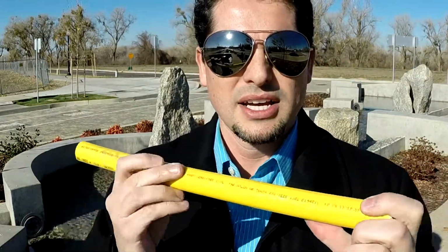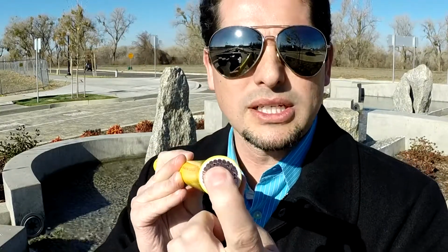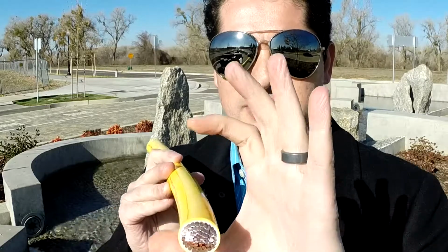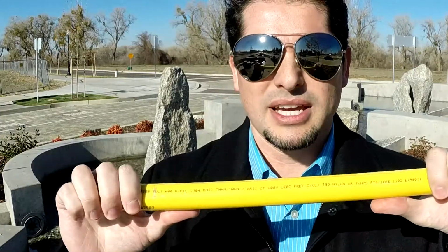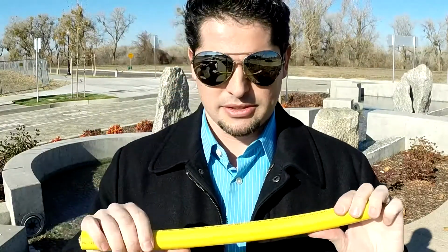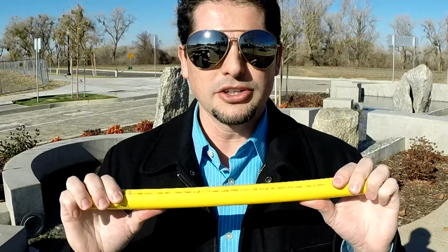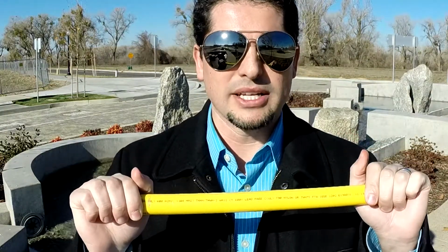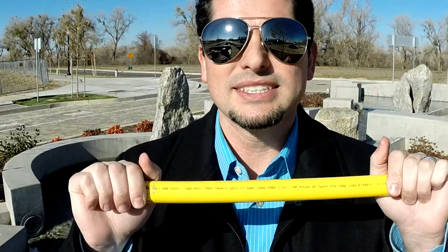For this cable size, this is a single conductor cable. All of these copper pieces you see in here act as one conductor for one phase. If you wanted to do 3-phase power, you might get a 3-conductor cable, which has an overall jacket, and you could have 3 of these cables within an overall jacket. That affects the ampacity of the cable. There are grouping derating factors also: if this cable is installed underground with a group of other cables nearby, heat will accumulate in the soil, and this has to be derated. Derated meaning rated with a lower ampacity. Even the depth that you put this cable underground affects its ampacity rating.